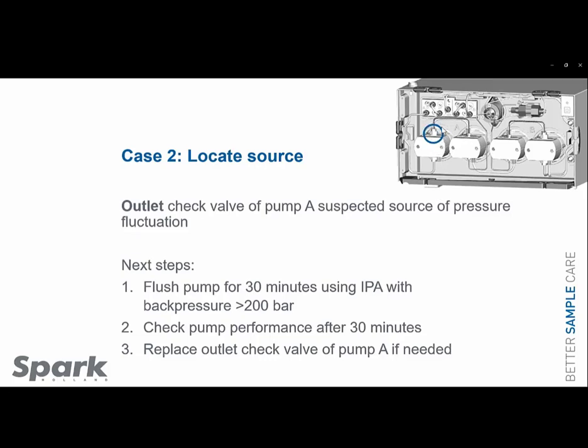The outlet check valve is located in here. We are not going to replace it directly. First, we will flush the pump for 30 minutes using 100% IPA, using a back pressure device of at least 200 bar. We check the pump performance after these 30 minutes. If the pump performance is okay, you can leave it this way. If not, we still are going to replace the outlet check valve of pump A.